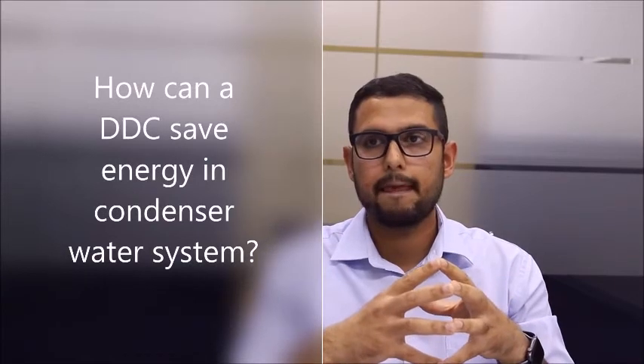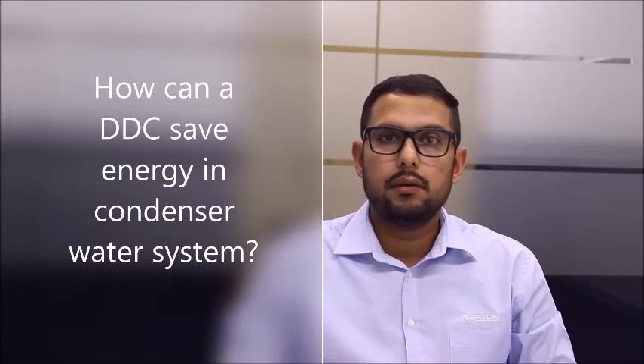Cool. So in the context of, say, a condenser water system where we have, for example, a cooling tower with one cooling tower fan and one condenser water pump, which is the simplest system that we've seen in terms of condenser water loops, how can a DDC help save energy? So what DDC will do is, let's look at the scenario first. As you have told me, there's a cooling tower which has got a fan, probably with a variable speed drive as well. It's got a pump with a variable speed drive, and the cooling tower is feeding the water to the package units or air conditioning units or other systems across the building.